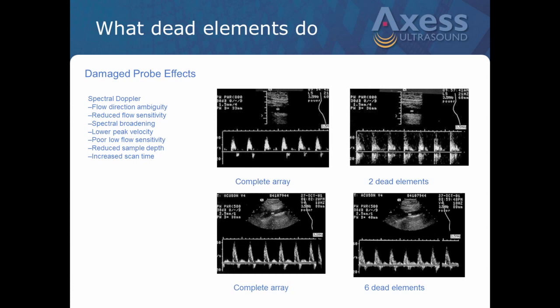One area where you'll really see a negative clinical effect is in Doppler. I make no bones about it: if you take a curved abdominal probe with 192 elements in a composite array, and 2, 3, even 4 are dead out on the outer edges, you're really not going to see much effect on clinical performance when looking at the liver or kidney. However, in Doppler it's a different story. If you look here on the left, we've got a complete array. This is a vascular image in this first case, showing a normal pulse Doppler wave—looks as it should, healthy patient.